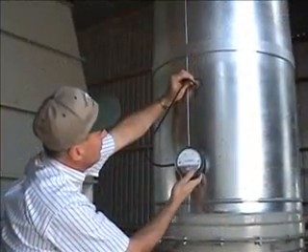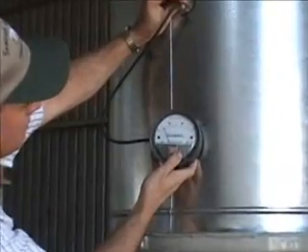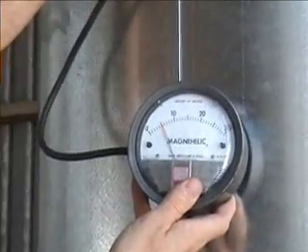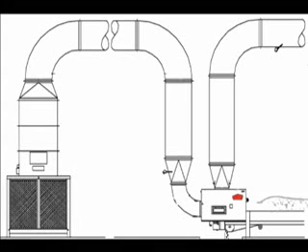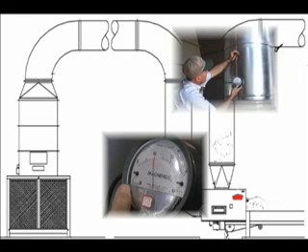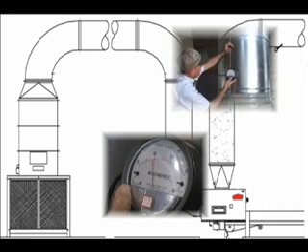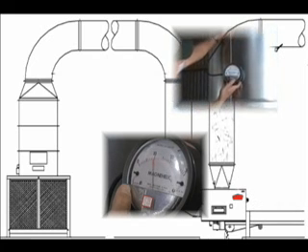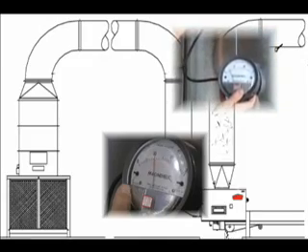In other situations, a pressure value makes more sense when it is compared to a pressure value at another location in the same air system. For instance, the difference in pressure between two points is sometimes referred to as pressure drop. Pressure drop can be thought of as a value to describe the resistance to air flow between two points. This value can change substantially when a cotton gin is idling and when cotton is flowing in the pipes.